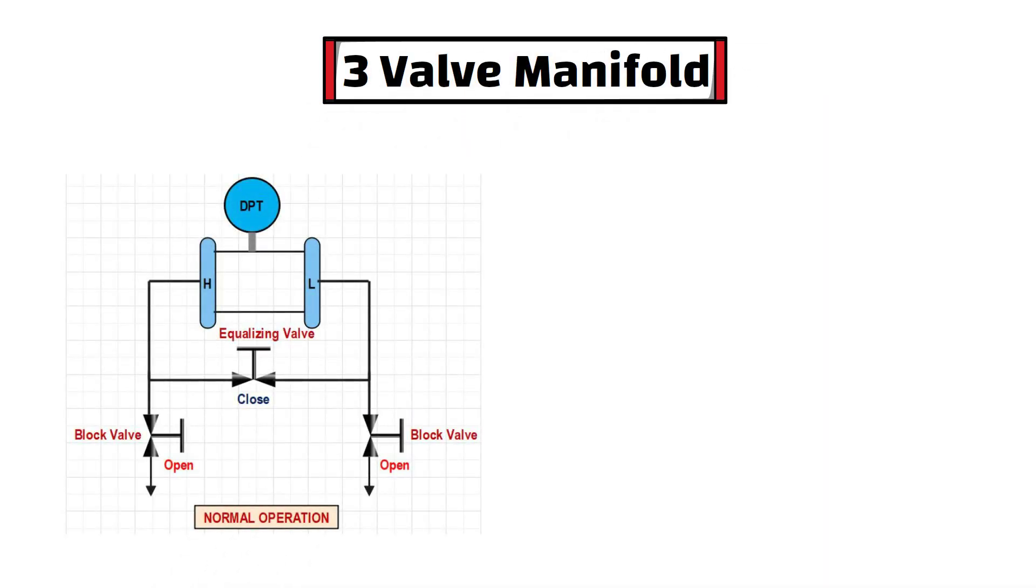First of all, let's take an example of three-valve manifold. As you can see in normal operation, both block valve is in open position and equalizing valve is in closed position.